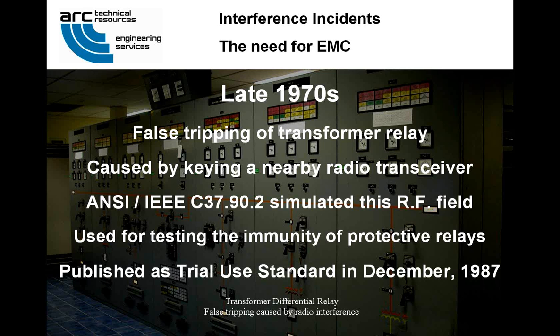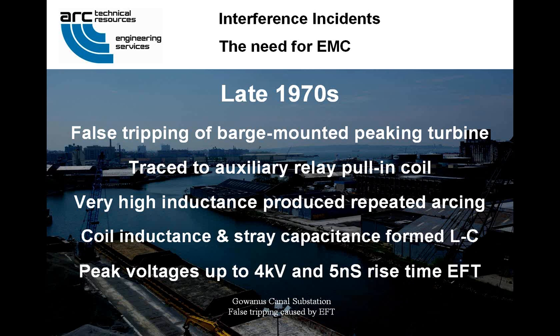Also in the late 70s, a false tripping of a barge-mounted peaking gas turbine generator occurred at the Gowanus substation in New York. It was traced to an auxiliary interlocking relay with very low battery drain in case the plant lost power. The relay's pull-in coil had very high inductance, 2 Henrys, to produce a strong magnetic field with very little excitation current. When the external circuit would attempt to de-energize this relay coil, the inductance and the stray capacitance of the control panel wiring created an LC circuit with discharging voltages up to 4 kV DC peak on the control wiring, rise times of 5 nanoseconds, and repetition rates of 2.5 or 5 kilohertz or higher. Simulation of this burst waveform was first published in IEEE standard C37.90.1 in the early 80s as electrical fast transient immunity testing for protective relays, and was cited in IEEE 1613 in 2003 for the evaluation of utility communications equipment.